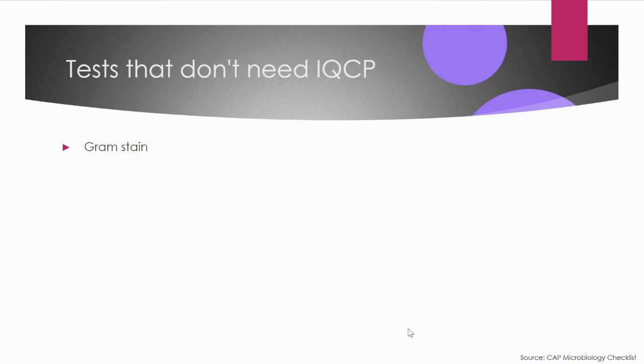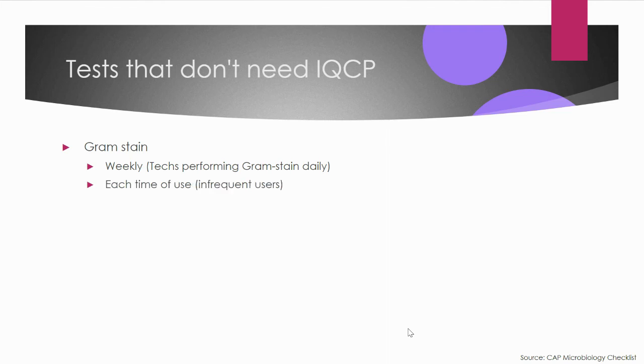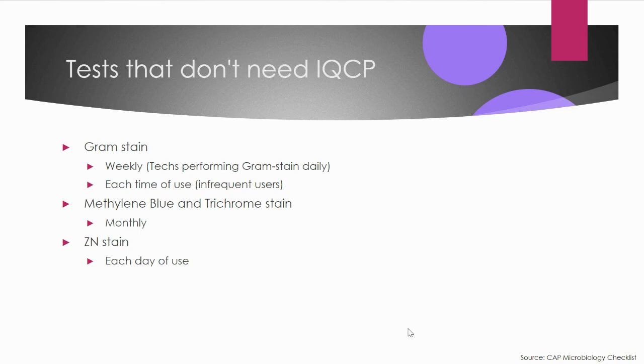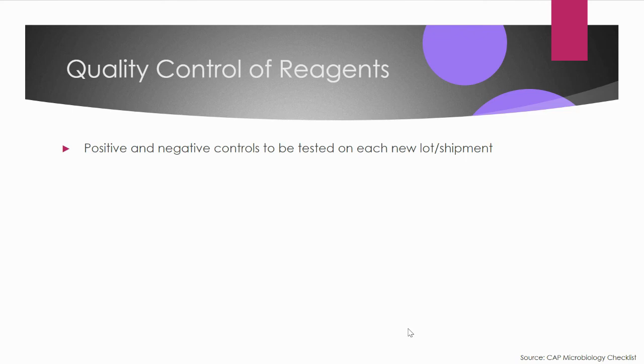Some tests do not qualify for IQCP and must follow CAP default. For gram stain, weekly QC is required if performed daily. If a technician performs gram stains very infrequently, QC should be done every time it is used. Methylene blue and trichrome stains require monthly QC. Ziehl-Neelsen stain requires QC each day of use, while fluorescent stains require QC each time of use.